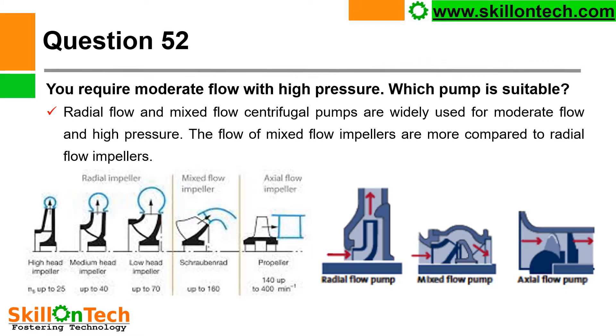Question 52: You require moderate flow with high pressure — which pump is suitable? You can see some pictures. Radial flow and mixed flow centrifugal pumps are widely used for moderate flow and high pressure. The flow of mixed flow impellers is greater compared to radial flow impellers. The specific speed of the pumps decides the type: for radial flow impellers, specific speed is up to 70; for mixed flow impellers, up to 160; and for axial flow impellers, up to 140 to 400 rpm.